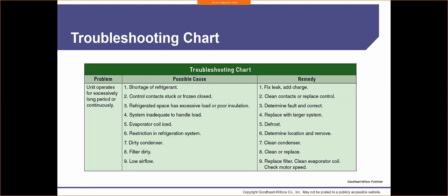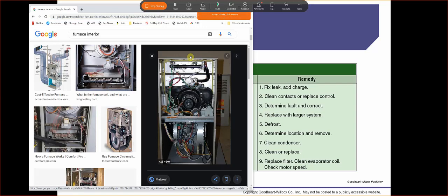Now, getting to the real sequence, the first thing we're going to turn on is the inducer motor. Let me see if I can pull up an image of a furnace, and then it'll be easier for me to talk about. So what we have here is a furnace. Don't be overwhelmed by it too much. This is actually not too complicated. It looks like there's a lot going on, and unfortunately, because of all the wiring and whatnot, there is, but overall it's real simple. The first thing we have is this furnace inducer right here. What this does is it's going to suck all the gases through a heat exchanger.